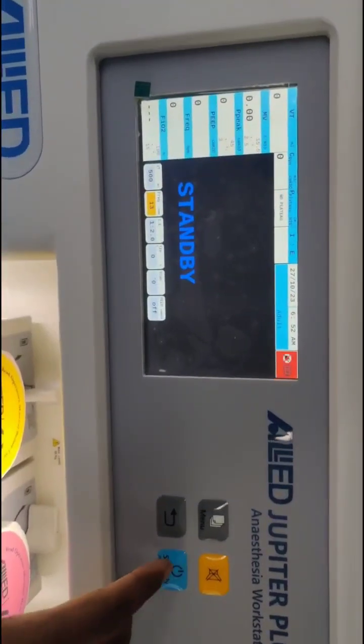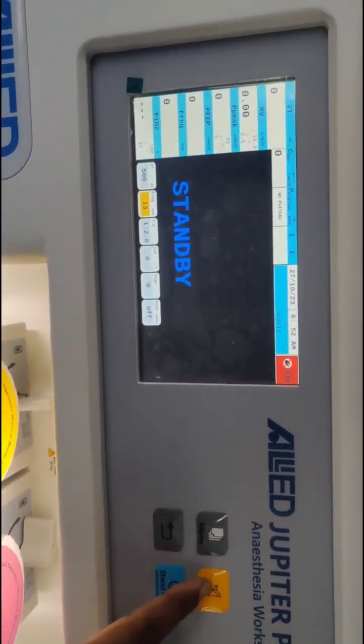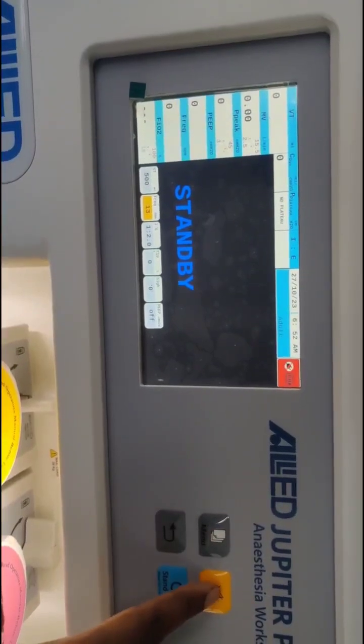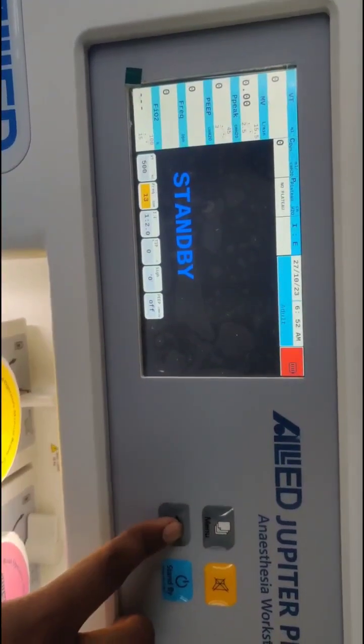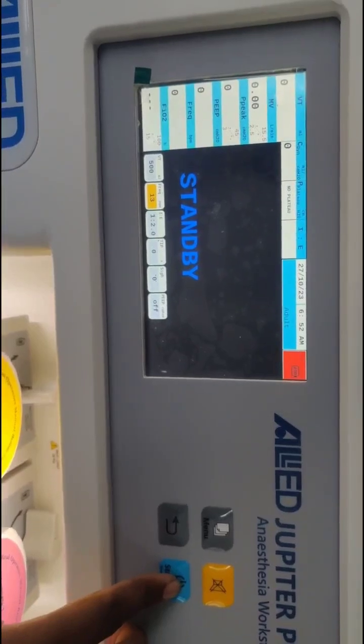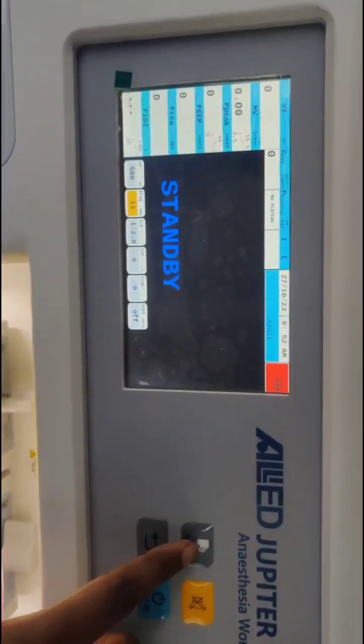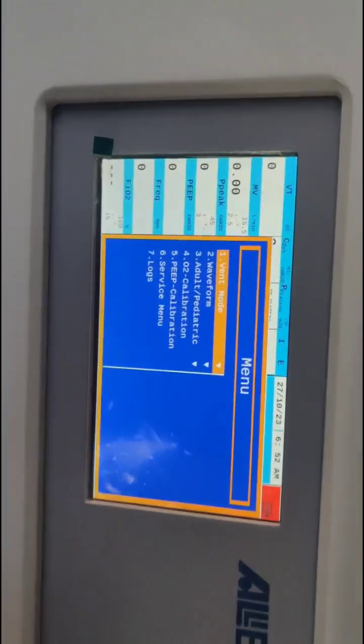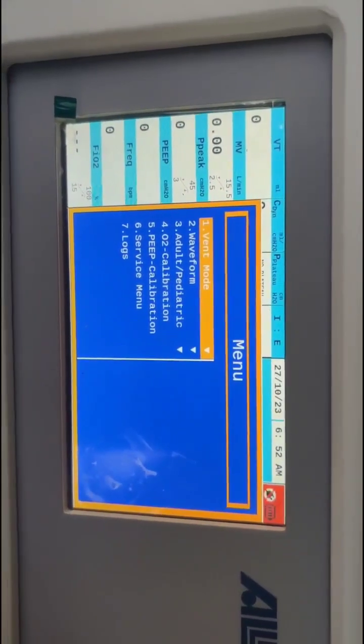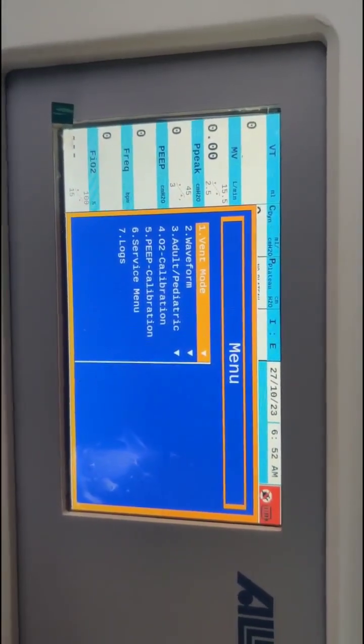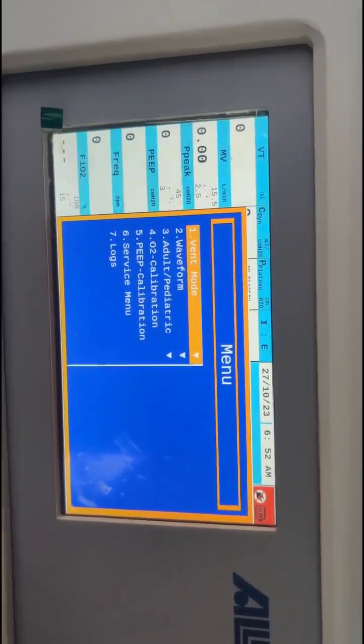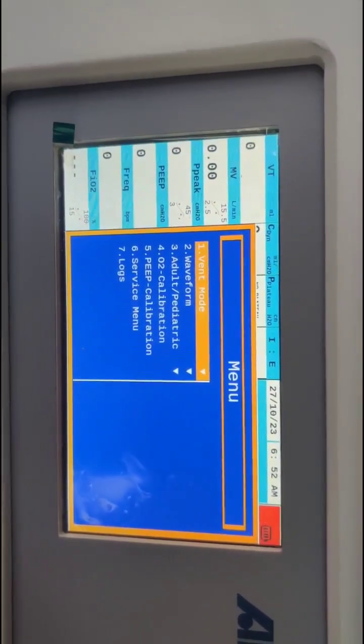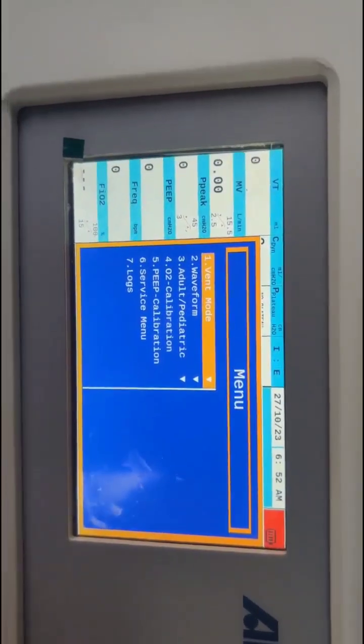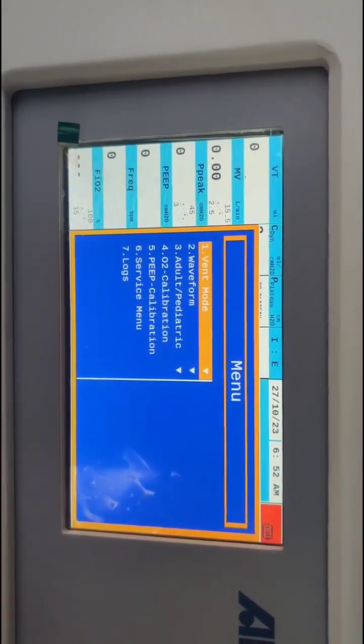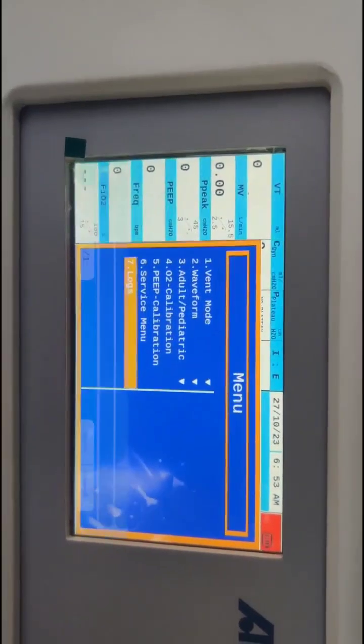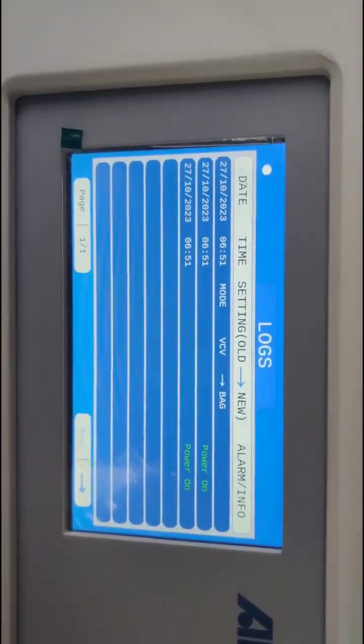We have given 4 buttons on the ventilator portion: the menu button, the alarm silence key, this one for cancelling any of the settings, and this one for putting the ventilator in standby mode. As soon as you press the menu button, you get all the options of ventilation modes. You get the waveforms option, the patient selection option, adult, pediatric, O2 calibration, that will be done by the service engineer, then PEEP calibration, service menu, and logs. We have 100 logs available in this, which show you all the alarms which have come up in the past or whatever settings you have done.